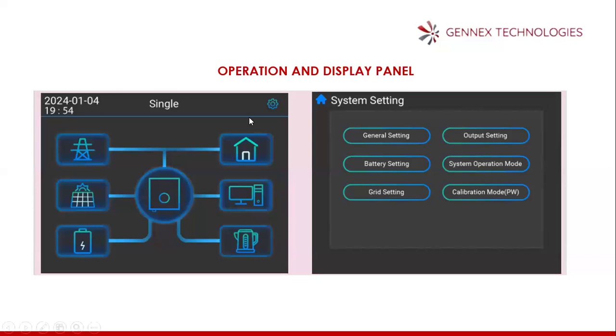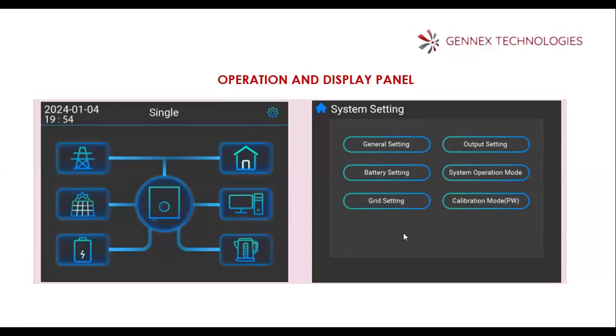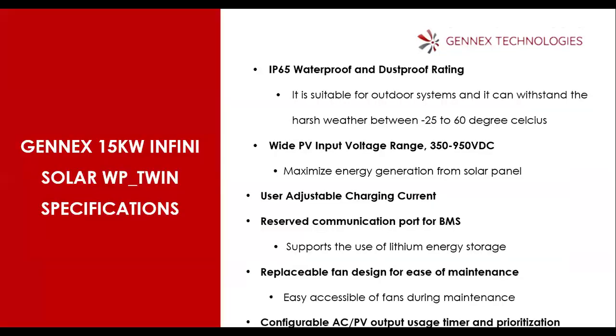So we have mentioned the inverter is IP65 waterproof and dustproof, and is suitable for outdoor system, and it can withstand the harsh weather between minus 25 degrees Celsius to about 60 degrees Celsius. And it has wide PV inputs. We have discussed that. Then it has the adjustable charging current. You can choose the charging current you want on the system. Maybe you don't want the inverter to consume more of the electricity you need from the public grid. You can reduce the charging current. Maybe your battery requires about 60 amps, but you don't want to be using more of the grid to charge the battery. You can reduce it to any level you like.